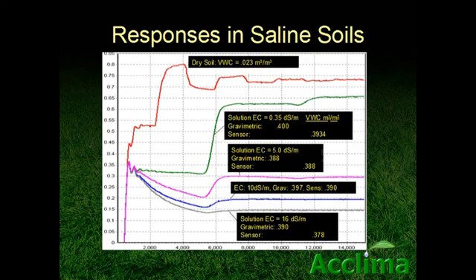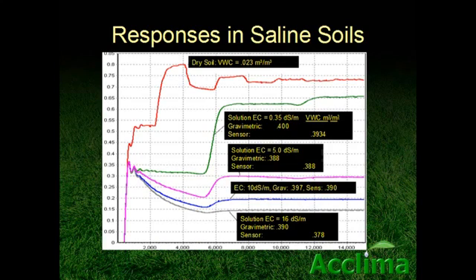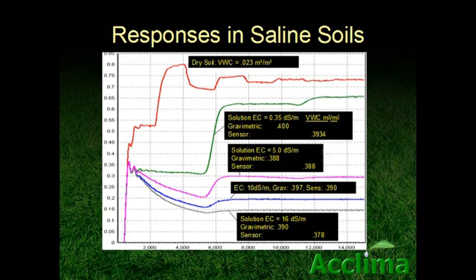Here are some untouched waveforms and readings from soil samples wetted with water of varying degrees of salt content. The gravimetric readings shown were made by carefully weighing the added water to dry silt of known density and residual water content. Note that the reflected wave from the dry soil sample has an abrupt inflection point — because of the low water content the reflected wave bandwidth is very high. You would not see such detail if a coax cable were involved. Note the accuracy of the readings where the water EC was 0.35, 5, and 10 deci-siemens per meter. At 16 deci-siemens per meter, the sensor underestimated the water content by about 1 percentage point — but this is not due to any flaw in the underlying principle, but rather is caused by the reflected wave being nearly dissipated by attenuation from the soil ions.